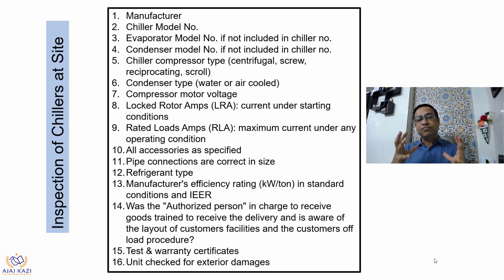Then the person who is supposed to receive the chiller has to be authorized. He should be competent. Otherwise, we don't want to do a clerical job here. We need to check technically. We also need to get a test and warranty certificate from the manufacturer. And obviously the most important thing is whether the unit has any exterior damage, or any component which is damaged or missing. These need to be checked.